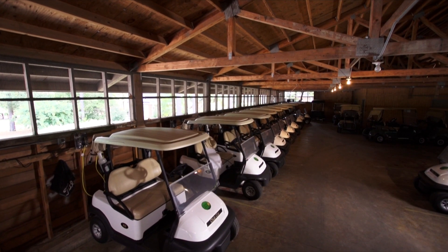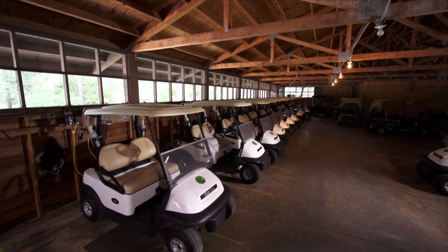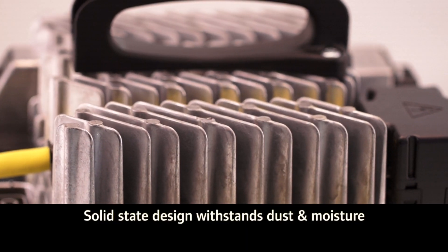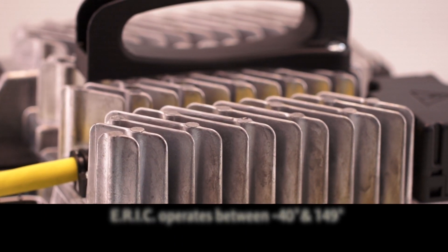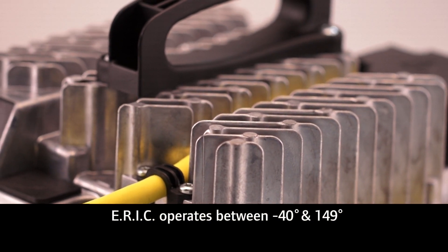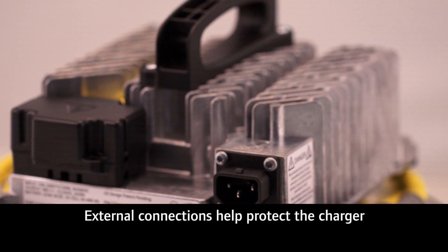And since we all know that cart barns aren't exactly free of dirt and debris, and that accidents have been known to happen, E.R.I.C. is capable of standing up to more than its share of punishment. E.R.I.C.'s solid-state design withstands dust and moisture and operates between minus 40 degrees to 149 degrees. And if a cord is snagged, external connections for AC and DC cords help protect the charger's internal components.